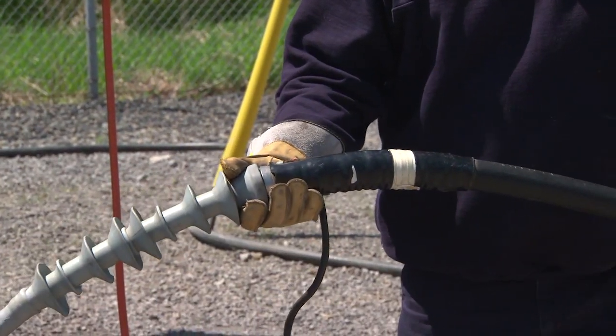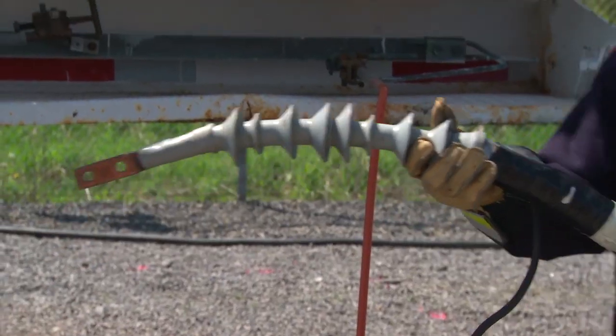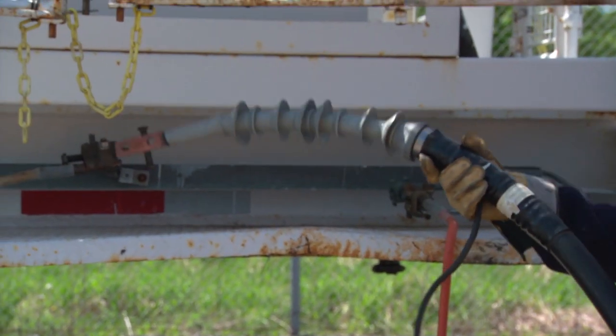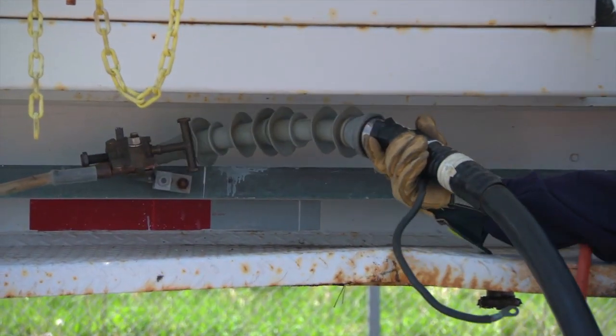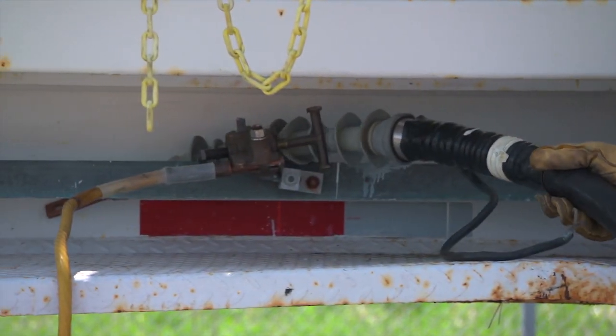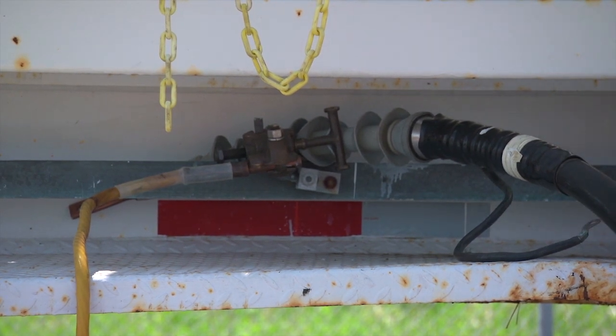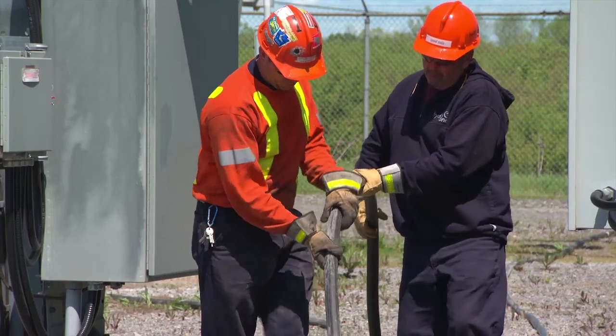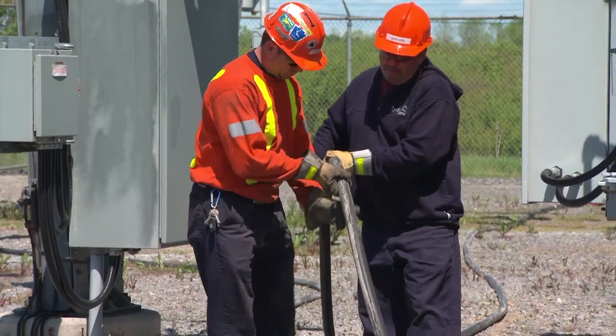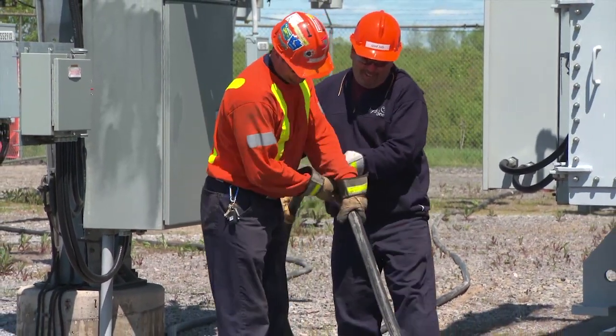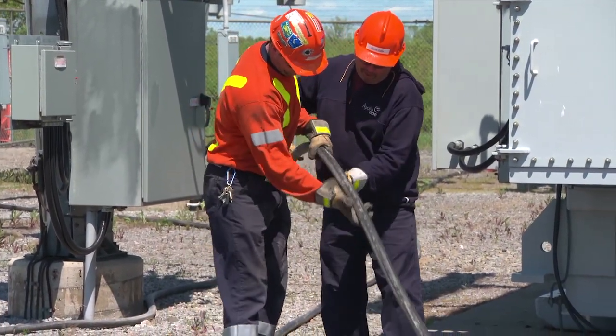Inspect the cable termination for damage, splits, cracks, or tracking. If necessary, clean the terminator with a clean cloth and isopropanol. Place the termination in a safe, secure location to prevent any damage. Inspect the concentric neutral, ensuring it has a good electrical connection.